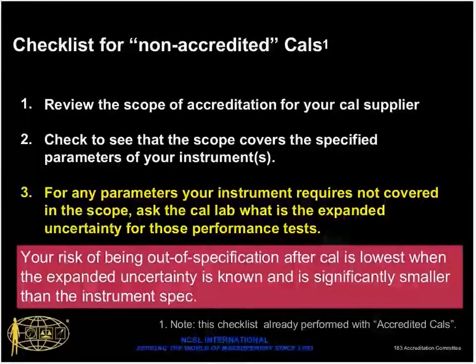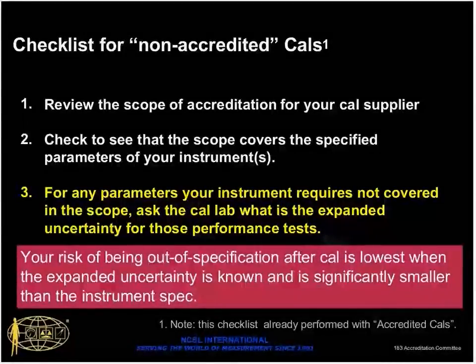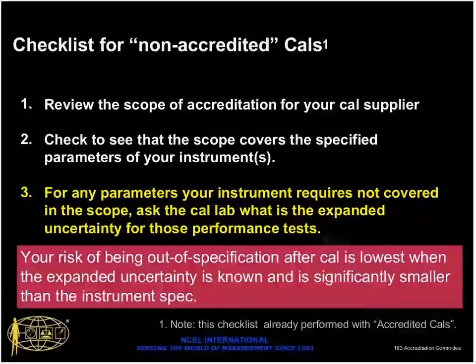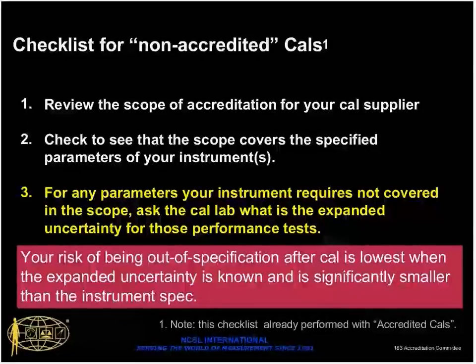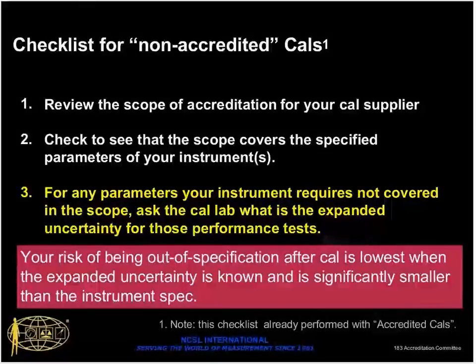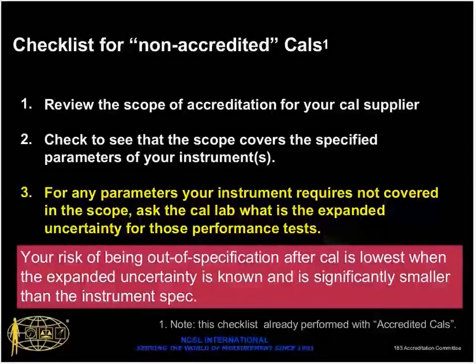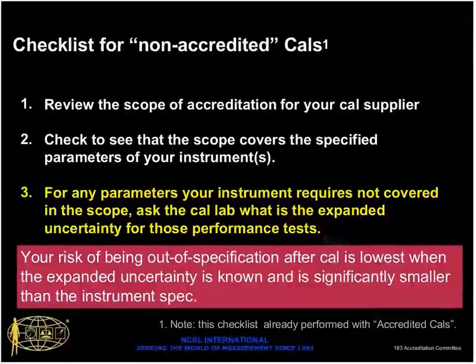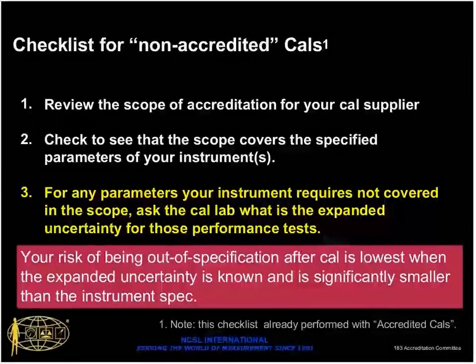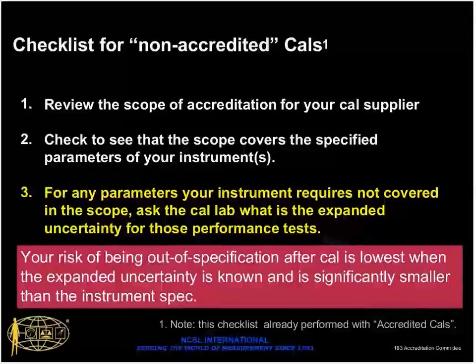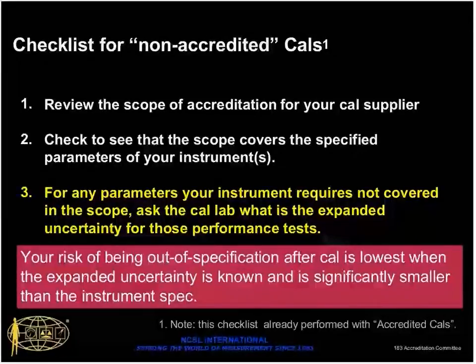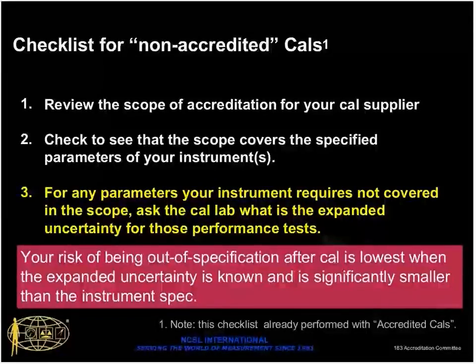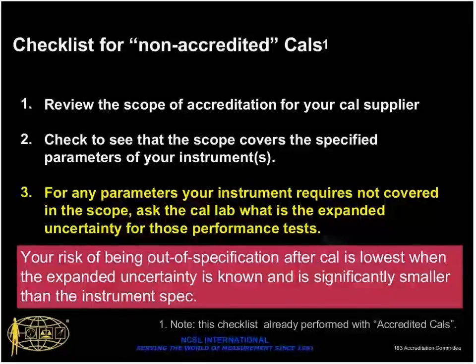So as Ryan and I are both trying to emphasize, when you send something in for calibration, you expect it to be measured. You expect them to tell you whether it passed or not and adjust if necessary. And the risk of it coming back out of specification is going to be lowest if the expanded uncertainty is known and is significantly smaller than the instrument spec.